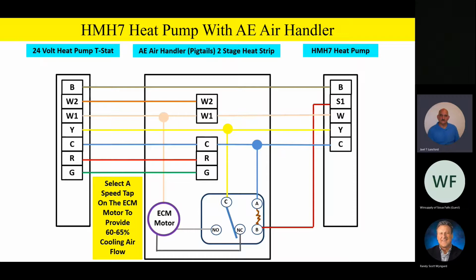So in an example, let's say, for instance, we had a 3-ton unit, 1,200 CFM on 100% airflow. 60% of 1,200 would be 720 CFM or real close to it. So we want to make sure and select a speed tap on the normally open contact of that relay to give us about 60% airflow when the unit's calling for reduced airflow.